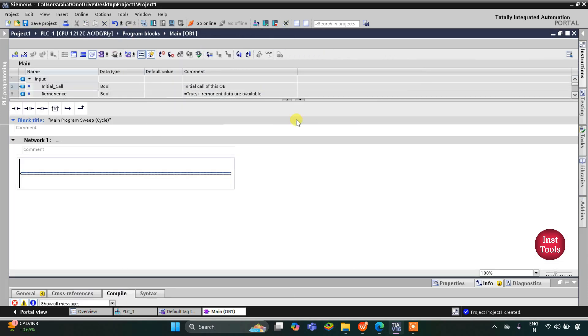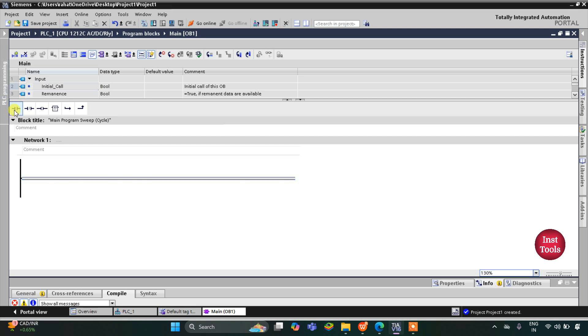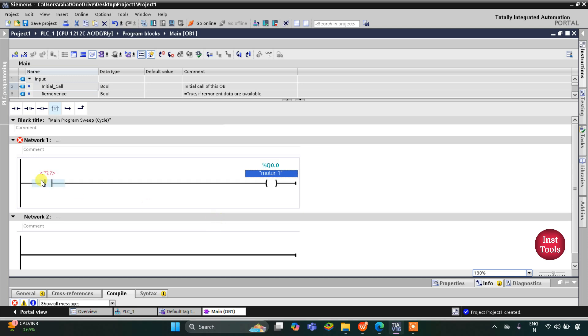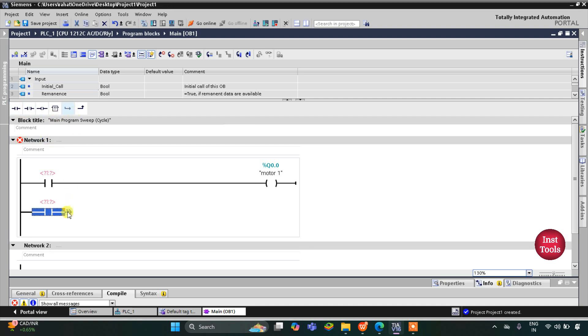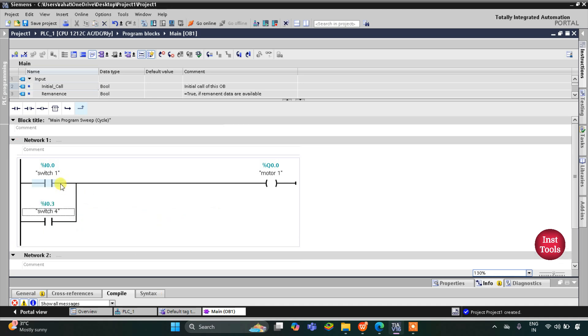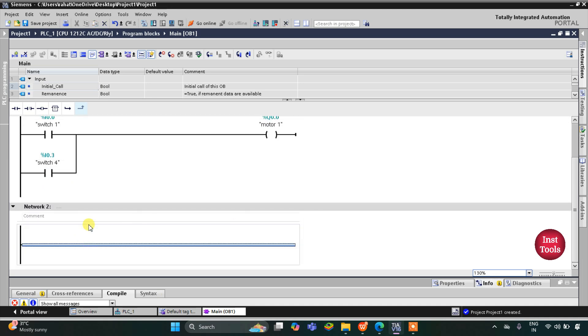Here we will draw the ladder diagram. I'll zoom in and insert a normally open contact, then insert a coil — this coil will be motor 1. Motor 1 will be on when switch 1 or switch 4 is on, so we will implement an OR logic gate. I'll insert an open branch here, then a normally open contact, and then close the branch. This normally open contact will be for switch 1 and the other for switch 4.